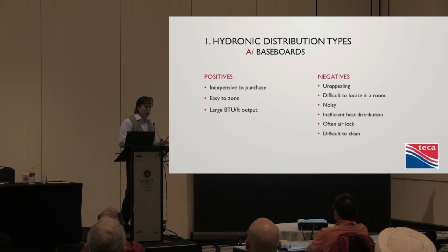When we consider we're operating at 180 degrees F, then if 1 foot gives you 600 BTUs per foot, that's pretty good. But we're running at 180 to get that. So it's an intensified amount of heat. Of course, we're going to talk about radiant later, which is going to take this whole room to offer the same amount of heat as a baseboard would do. So obviously the intensity of heat is a lot less with radiant.